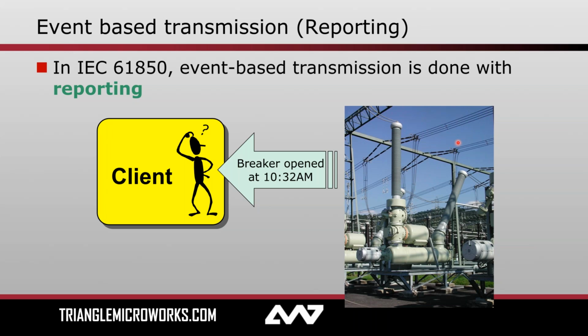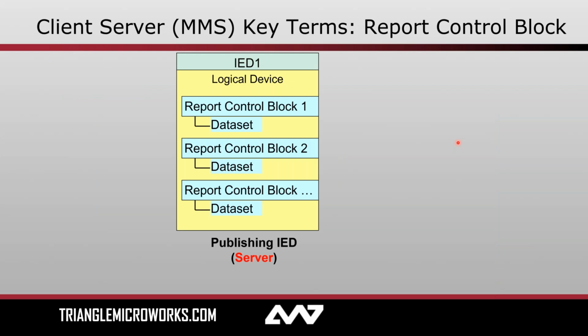It supports event-based reporting. So in order to do this, the client is going to reach out to the server and establish a connection. And then as data actually changes, it'll be passed up to the client. So how does that actually work? Well, if we look at this example here, we have an IED represented by this large box, and on it a logical device and a group of configured report control blocks. Each one of these report control blocks has an associated data set.